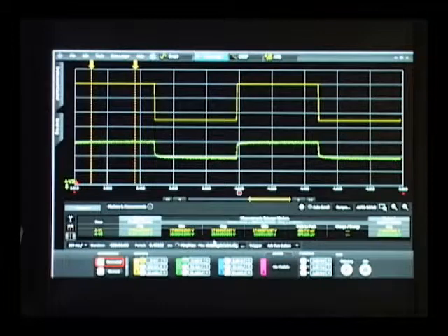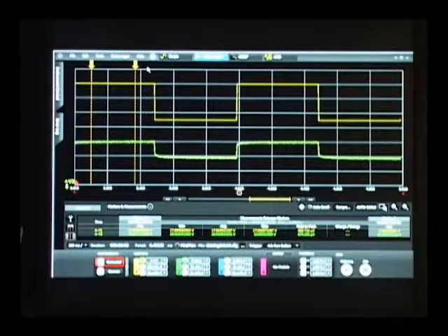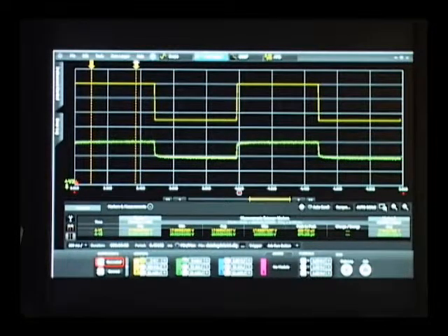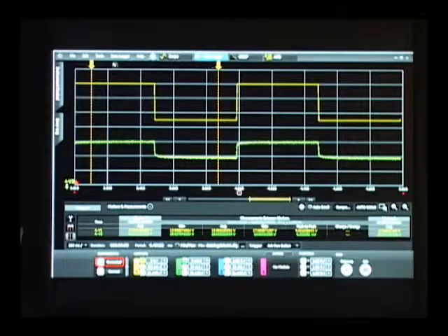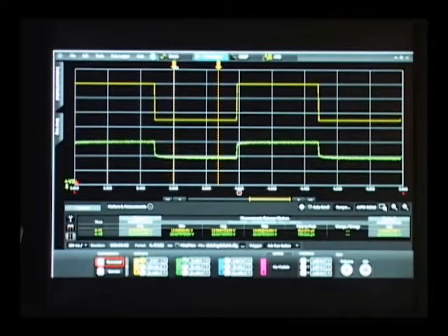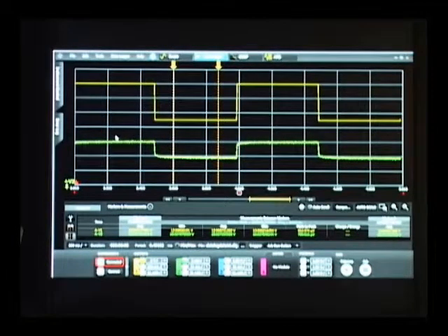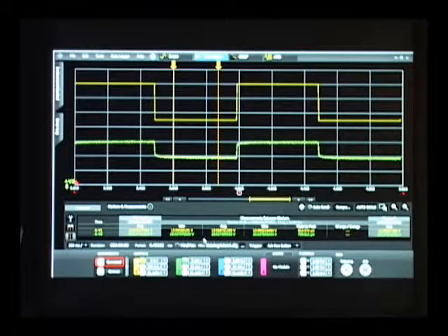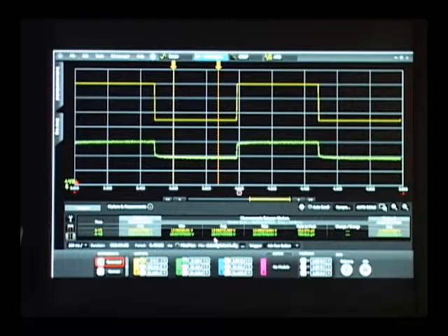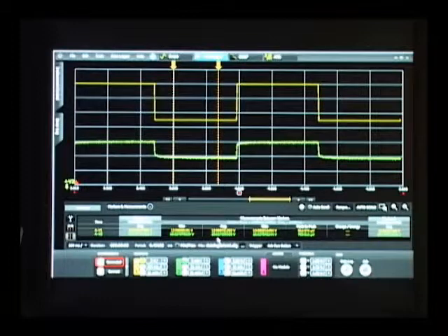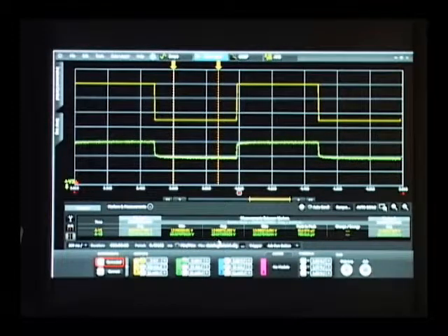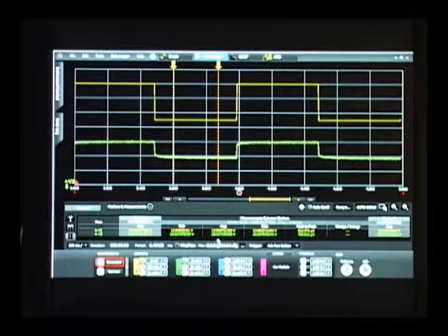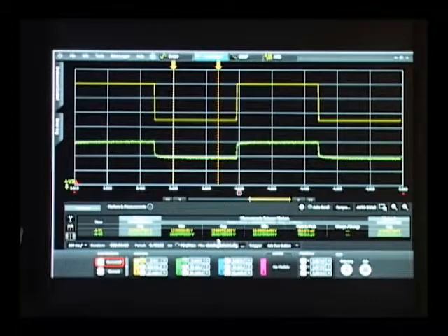Now let me move the markers to a low line condition. And now I find down here again in the numerical results, I now have about 10.028 volts. So I'm seeing about 5 millivolts of line regulation.